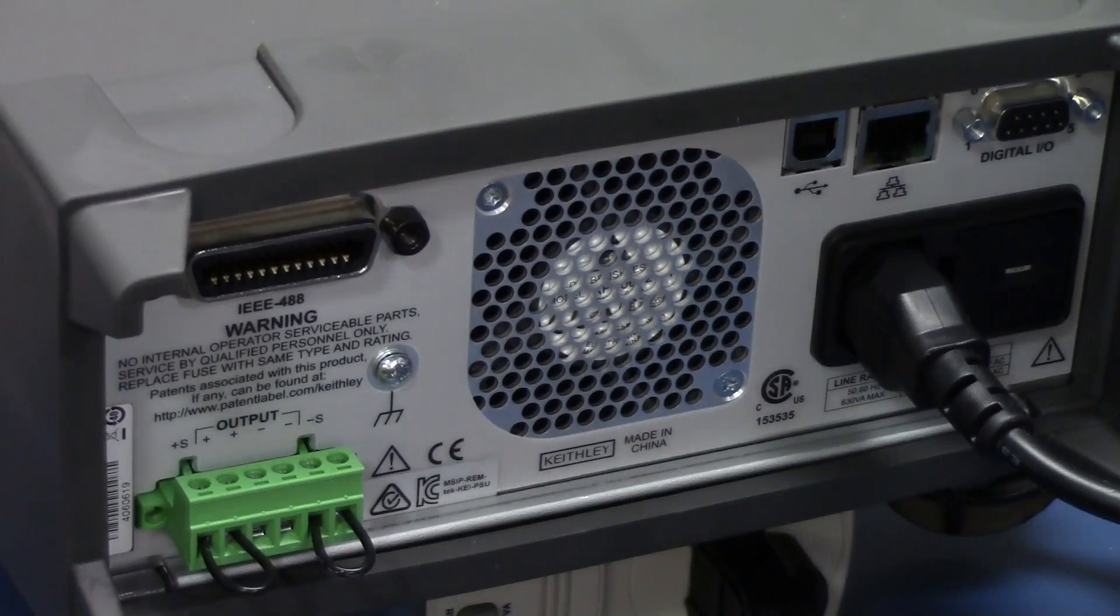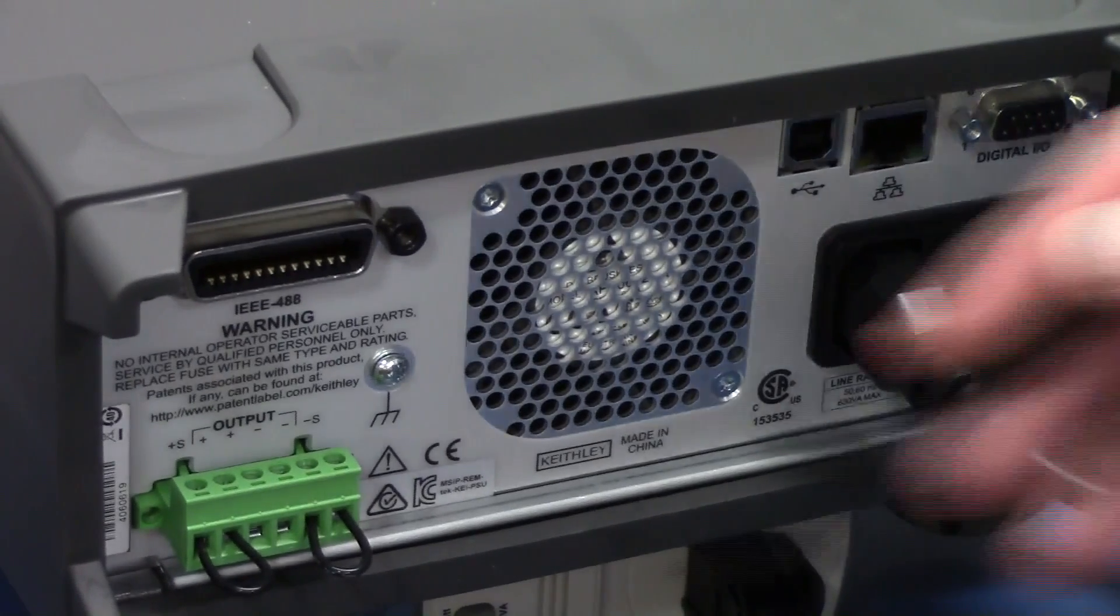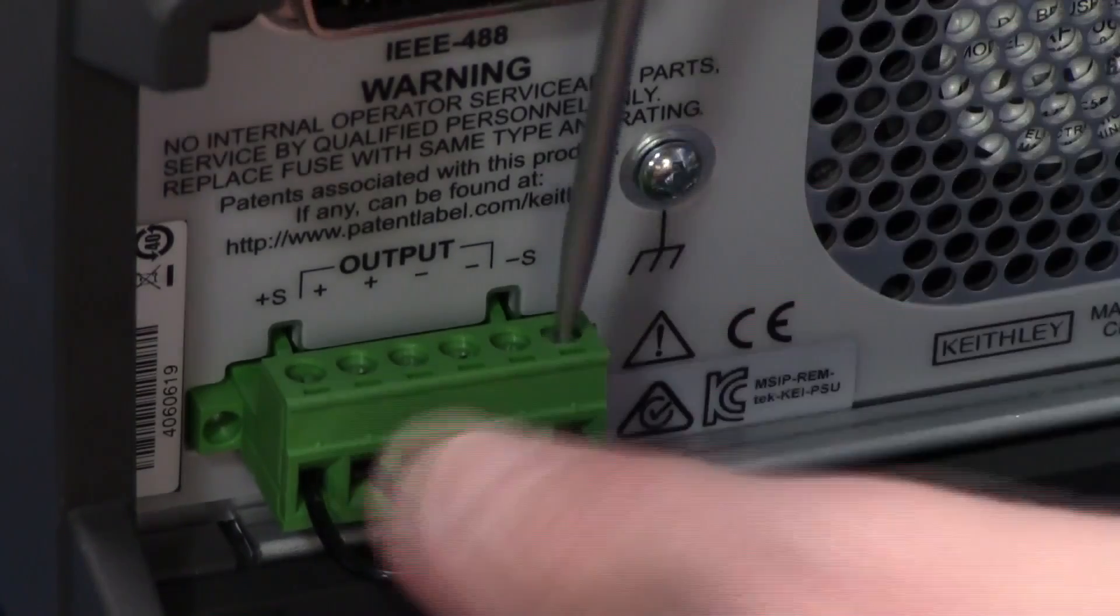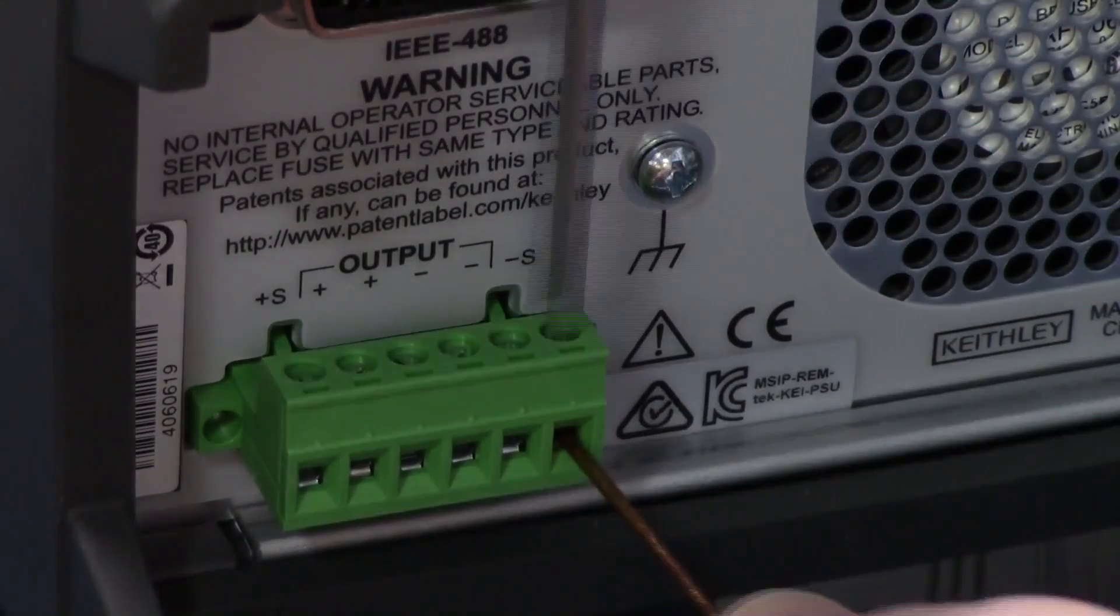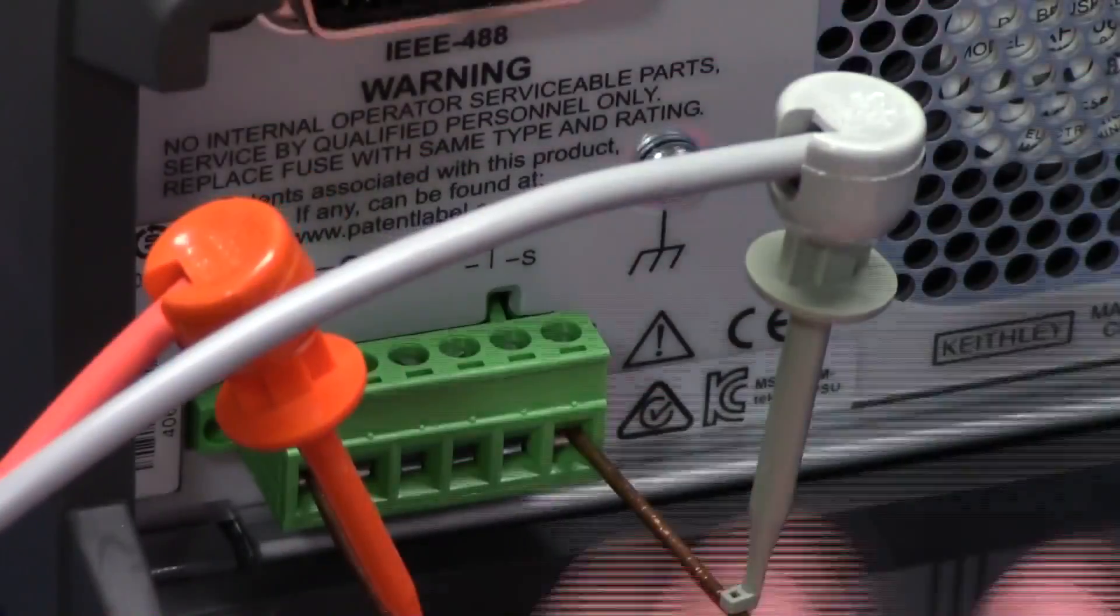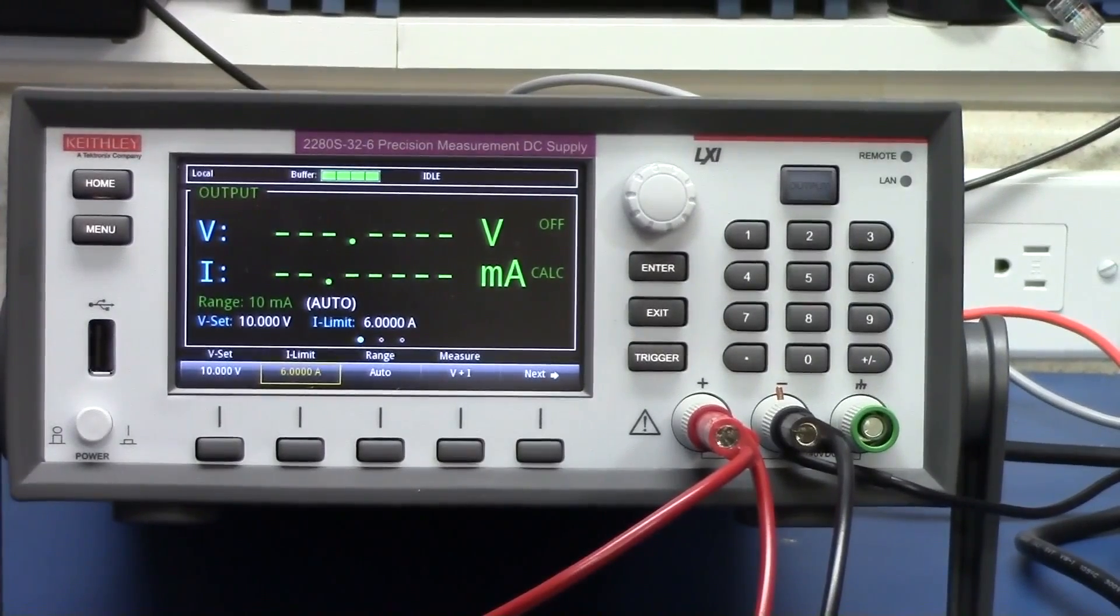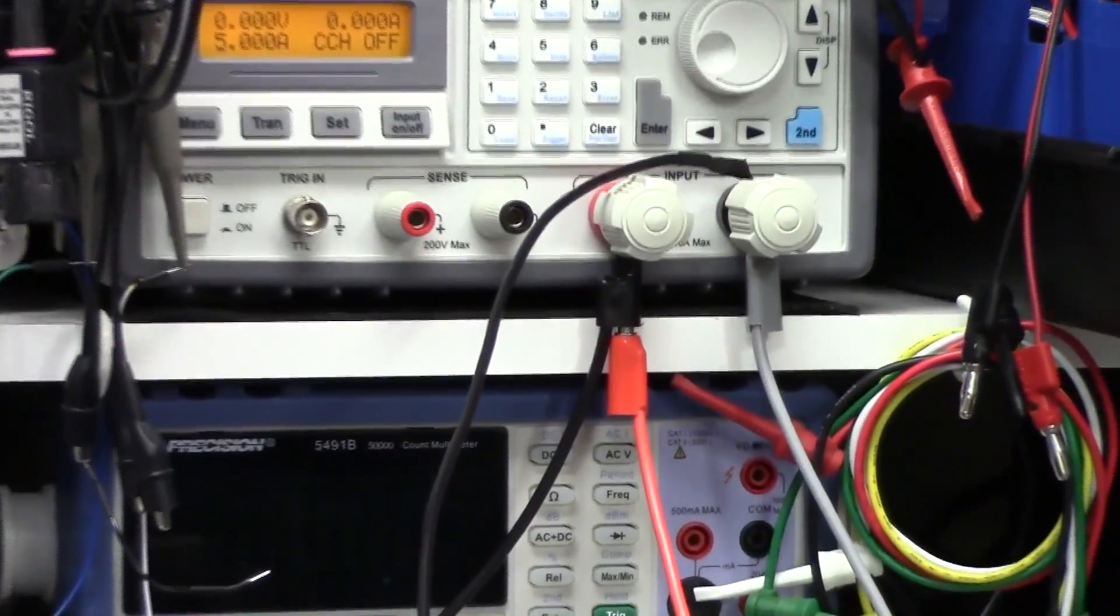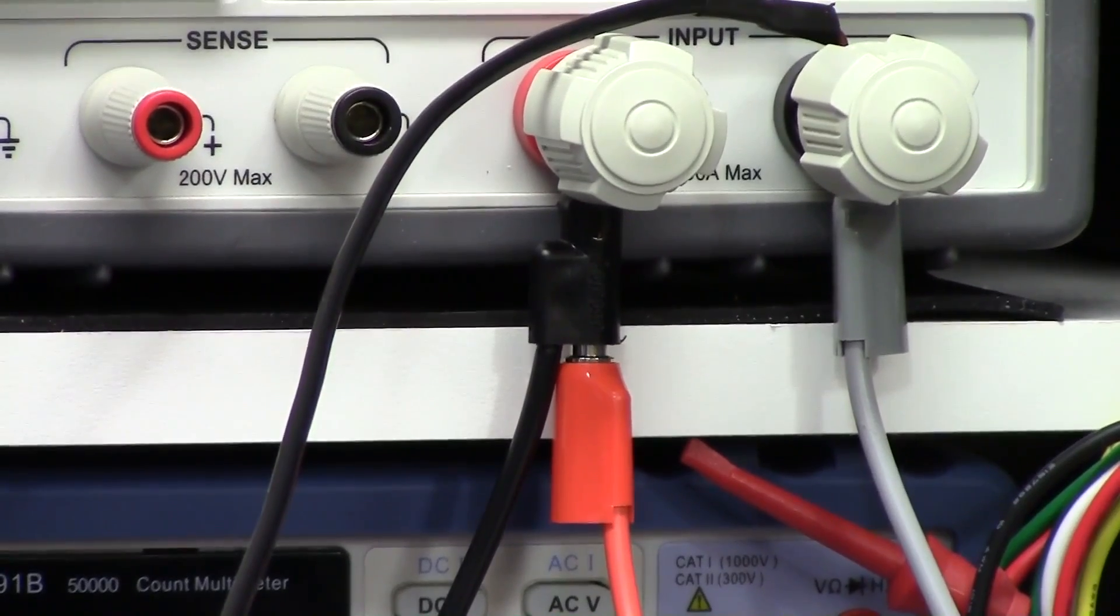So, real quick, let's swap out the jumpers on the back that were pre-installed for the remote sense and put it into remote sense mode. We're now connected up with the Agilent monitoring the output terminals of the power supply and the power supply's remote sense terminals connected up to the input of the electronic load. Let's see how this behaves.